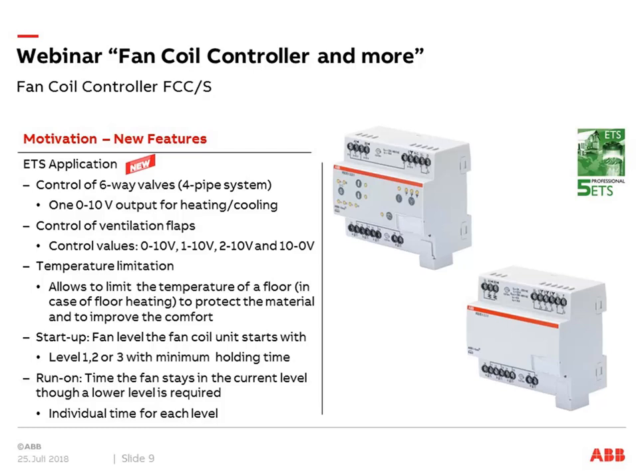A new feature, also a request from customers, is temperature limitation. The inputs can be used for temperature inputs — for example, connecting a floor temperature sensor to measure floor temperature, which is relevant for floor heating to limit the floor temperature and avoid damage or discomfort. You connect the temperature sensor and program a temperature limit that will not be exceeded during room temperature control. This is a very common demand, and is now directly possible in the component.